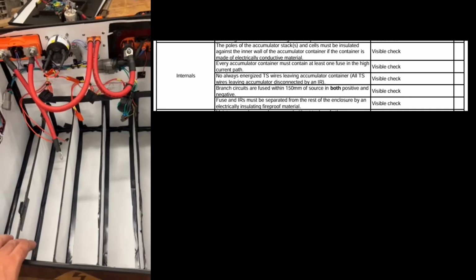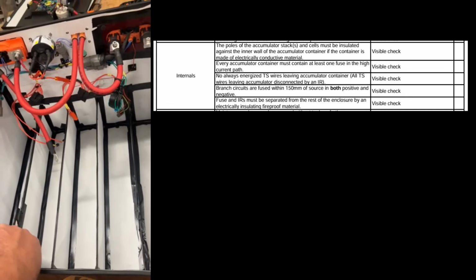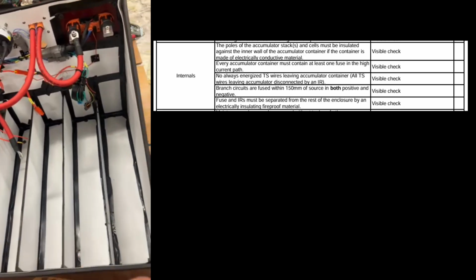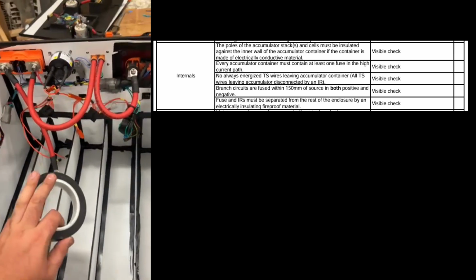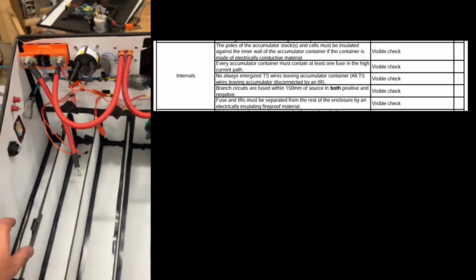Bus bars are spot welded together of copper and nickel, and those bus bars are spot welded to the cells, but there is no solder in the high current path in the modules or anywhere else in the battery. You can see the white Formex GK10 used as an insulating barrier between our cell stacks and walls. We also use black Kapton tape to fill in all the gaps, and white Formex insulation on our lid.